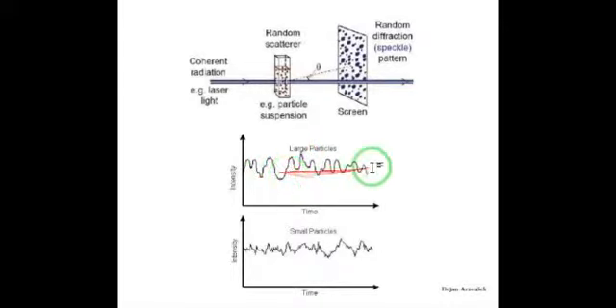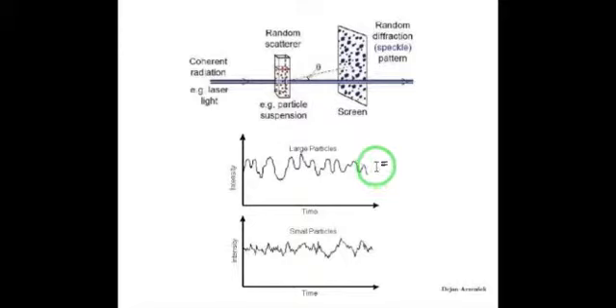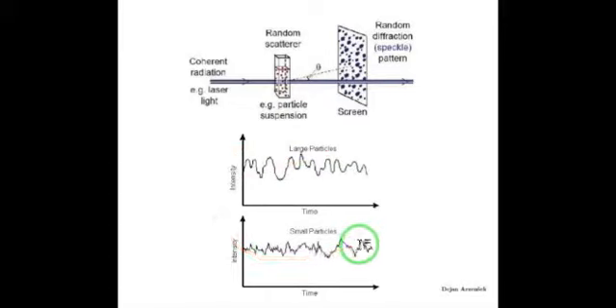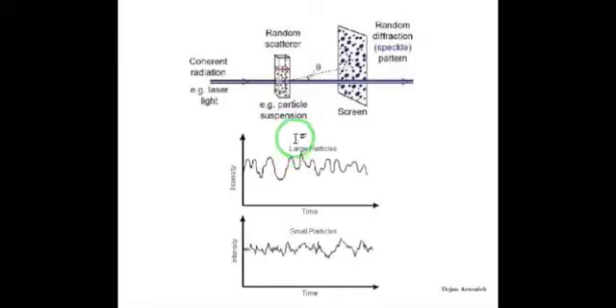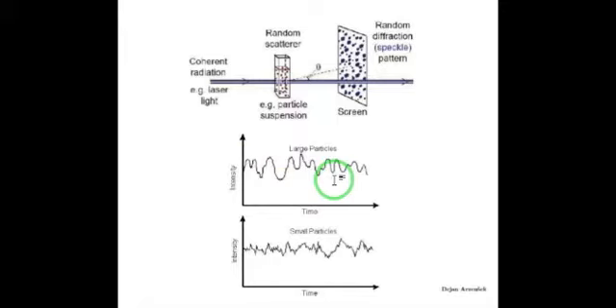You see slower changes in the intensity of the scattered light for larger particles. These two randomly measured intensity signals may at first seem to give you no information about size, but they are the key and most important elements for our analysis. The slow pattern in the change of intensity is exactly caused by the larger size of the particles, while smaller particles produce more rapidly changing patterns. These two patterns differ precisely due to the difference in particle size.